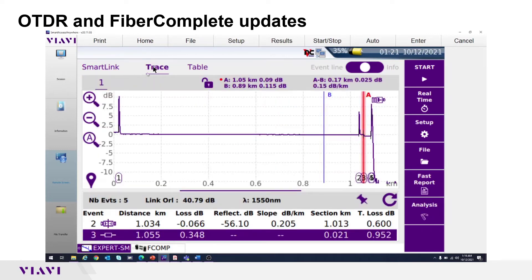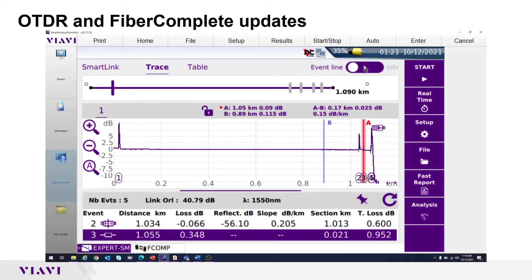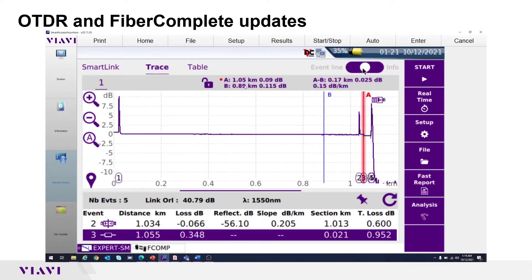If multiple wavelengths were used, there would be a one, two, and three displayed. One is underlined; only 1550 was shot, so there is only a number one here for the 1550 nanometer trace. There is also a button at the top — press it and there are three views: trace information is displayed, then an event line, then more trace is displayed and the toolbar goes away.